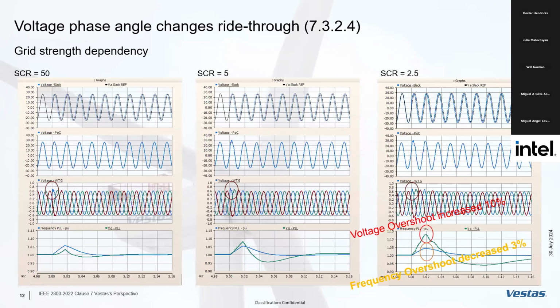In the next slide, I try to illustrate how the same PLL will also react differently depending on the grid strength. So the same PLL could also react differently, configured in the exact same way, if the grid strength is different. So this is important to keep in mind, because there is a false conception that some of the OEM technologies have some sort of protection that is monitoring phase jump, and that's not true. At least for Vestas, there is no such thing as a phase jump protection where you can put a number and then you trip for a certain degree of phase jump.